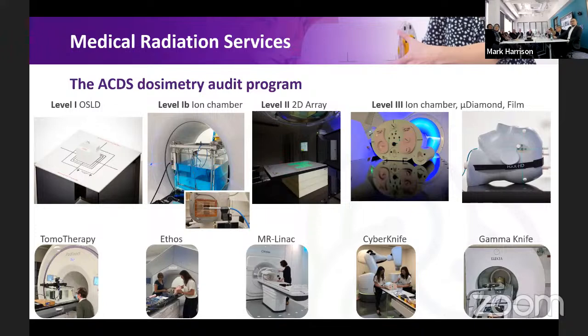And we've also talked briefly about different technologies, changing technology in the space. On the bottom left, we have a tomotherapy unit, which is essentially a 6 MV accelerator guide, sometimes a 4 MV, set up in what looks very like a CT housing. And that acceleration device moves around the patient, and the patient moves through the bore of the delivery system. And Ethos is a similar brand new piece of kit that's come out most recently, often able to be installed in less shielded rooms because there's more radiation shielding that comes with the instrument itself. On the higher-end tech end, we have an MR Linac, very new, very difficult to audit because you have to make sure you don't have any ferrous materials in your audit phantom.